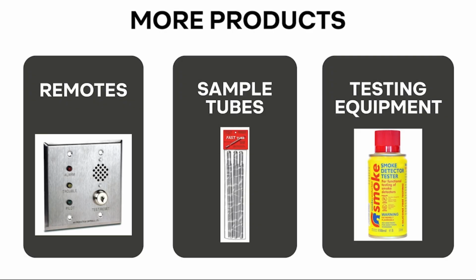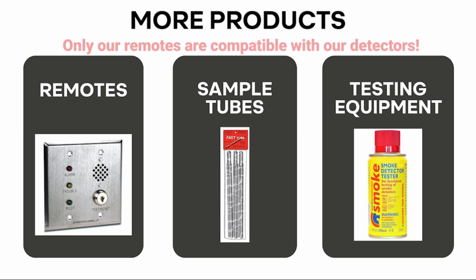The APC duct smoke detector line is complemented by remote accessories, sampling tubes, and testing products. Remote accessories are usually required by inspectors and save time and costs. If a duct smoke detector is not wired to a fire alarm system or a remote test station, when the unit goes into alarm, the end user would have to manually reset the unit, usually located in a ceiling or a rooftop. Providing remote accessories is an easy way to provide excellent customer service and added benefits to the end user. Please remember, only Air Products and Controls remote accessories are compatible with APC duct smoke detectors.